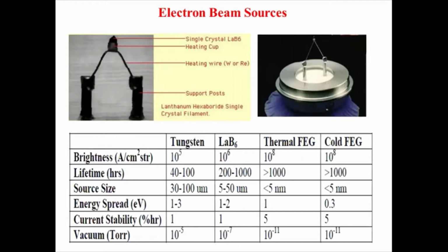So what is the minimum amount of energy required to remove an electron? That is the work function. So the minimum the energy, the minimum will be the temperature you require. So the operating temperatures are also different for tungsten and LaB6. And if you have the pure field emission, then you also get what is the energy spread.